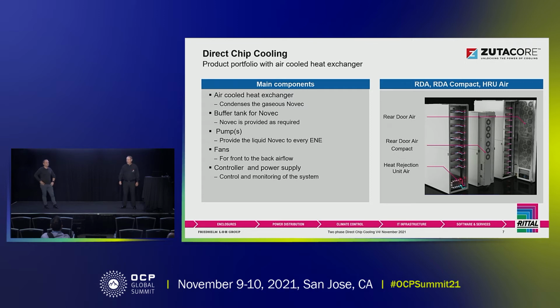They can be on the back of the rack, like rear doors. You can see a full rear door or a half rear door, depending on the power that needs to be cooled. It could also be on the bottom of the rack. We have a 6U air one, a 6U water one, and a 2U water one that can cool up to 40 kilowatts of CPU power in a rack.